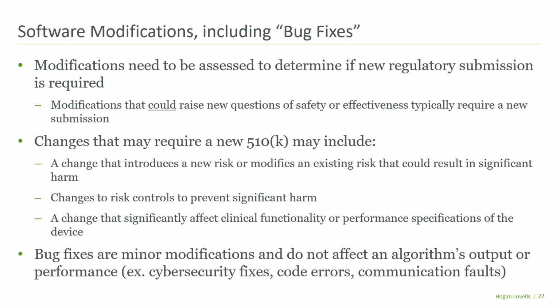That's acceptable. A change that introduces a new risk or modifies an existing risk that could result in significant harm would be a new 510K. Changes to risk controls to prevent significant harm, that could be a new 510K. A change that significantly affects clinical functionality or performance specifications, likely a new 510K.